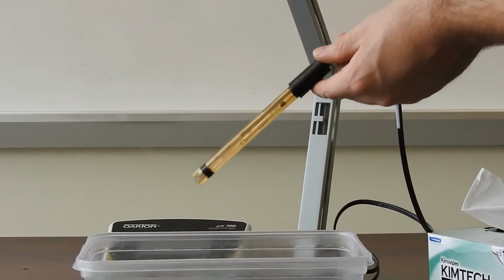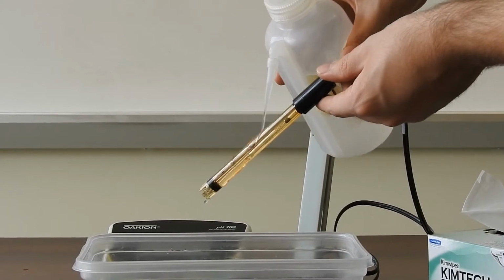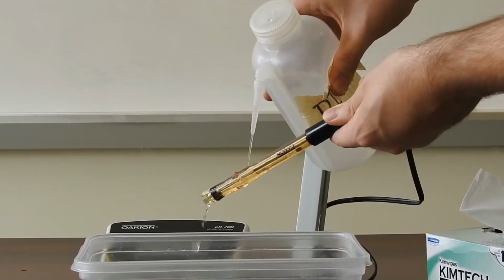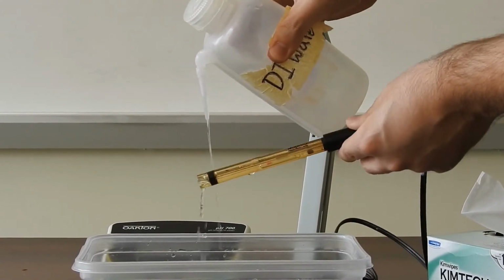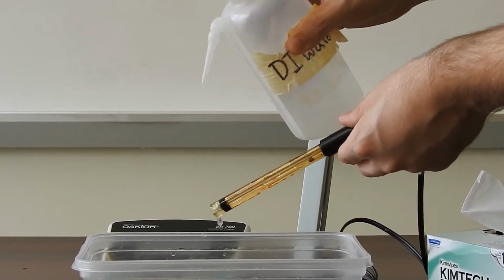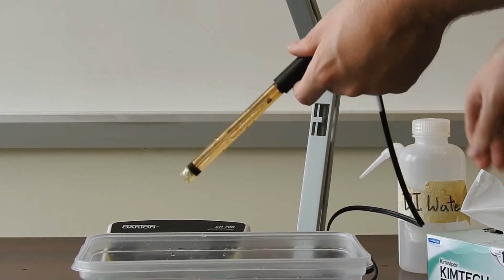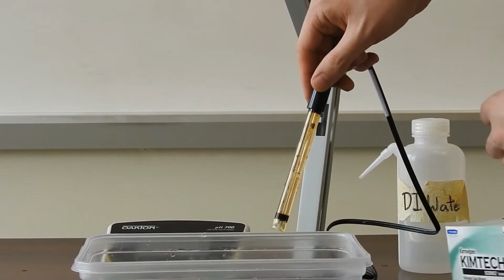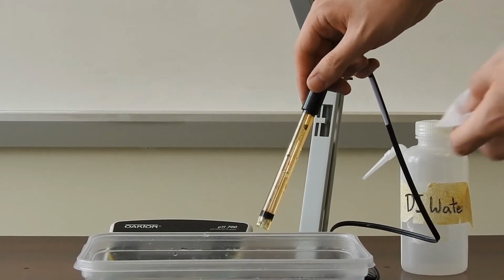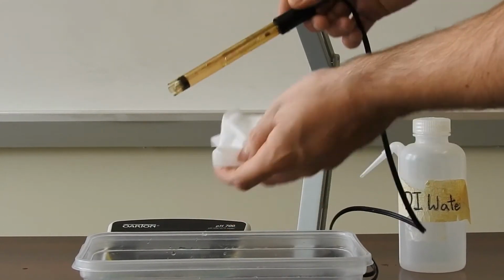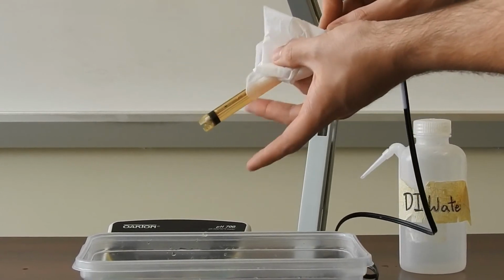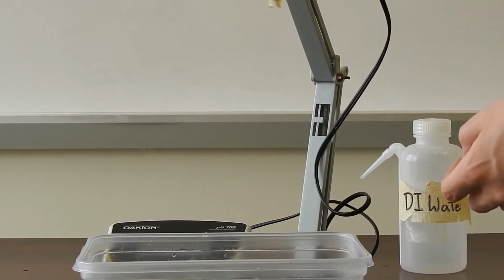And then the next step is to rinse the probe with DI water, just to make sure that you get rid of any of the remaining storage solution on all parts of the probe and make sure that it's nice and clean. You can also use a Kimwipe to dry it, as with other methods. Just be gentle and make sure that you're not damaging the end of the probe. So getting that excess water off, and then you can hook it back up on that suspension arm when it's not in use.